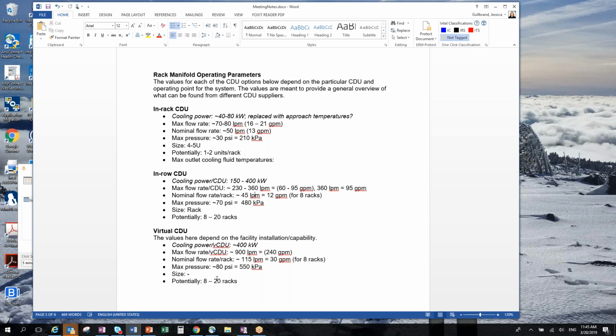One comment on that: the 80 psi number, I'm sure, is correct, but the manifold's not going to see 80 psi, right? That's the facility level pump pressure output probably, the manifold won't see that. That's important from a testing perspective and a burst pressure perspective. Our pressure spec has to be in line with that. If we say the manifold has to be specified to withstand 3x or 5x of 80 psi, that's very different than 30 psi, so we need to make sure that's clear.